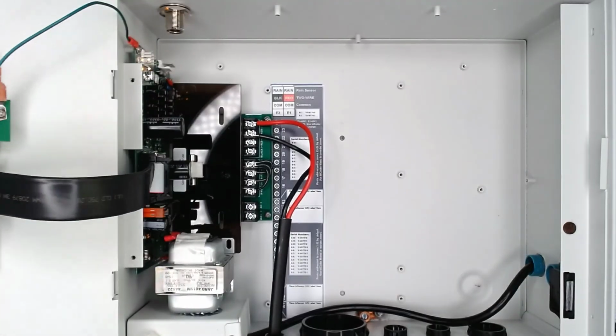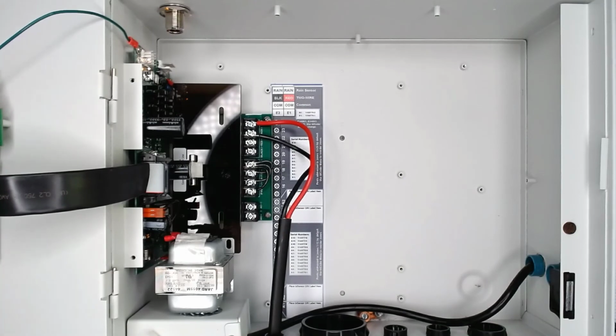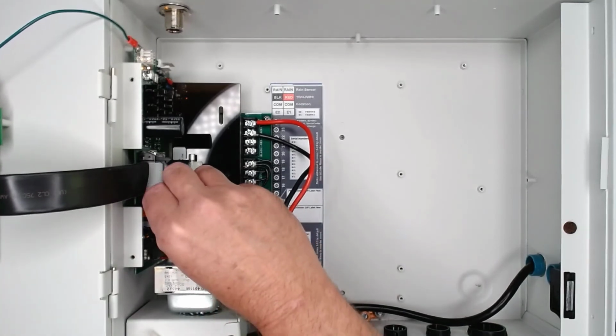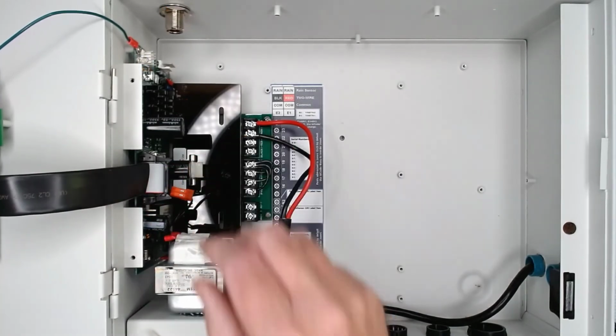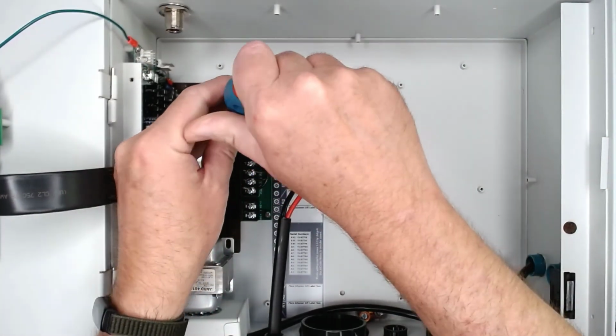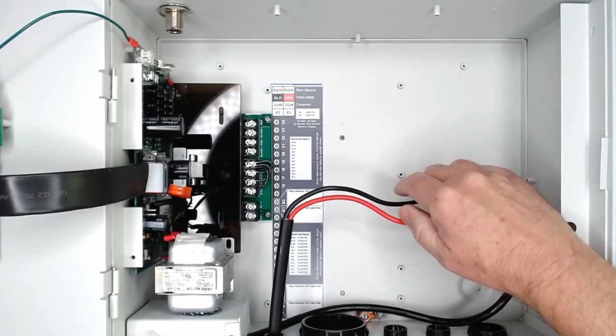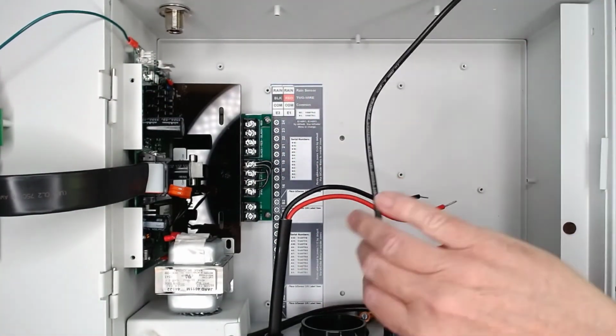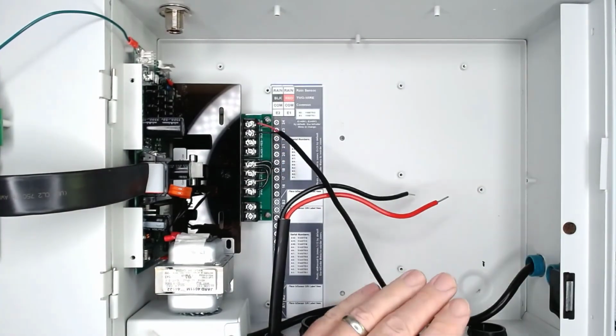Anytime you work on the 2-wire path, power down the controller. Unplugging the controller, turning off the circuit breaker, or disconnecting the orange plug on the control board all can power down the controller. With the power off, I can disconnect the existing wire path from the terminals and set those aside. I'll connect the soil moisture sensor to the red and black 2-wire terminals, making it the only wire connected to the controller.